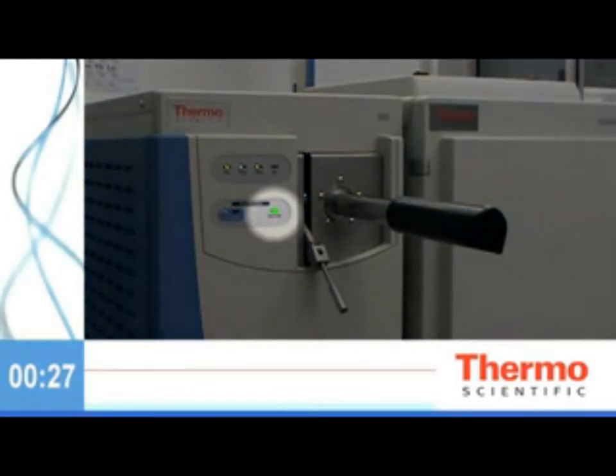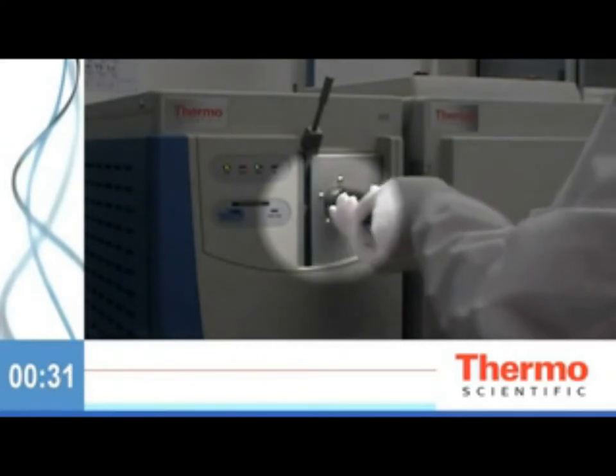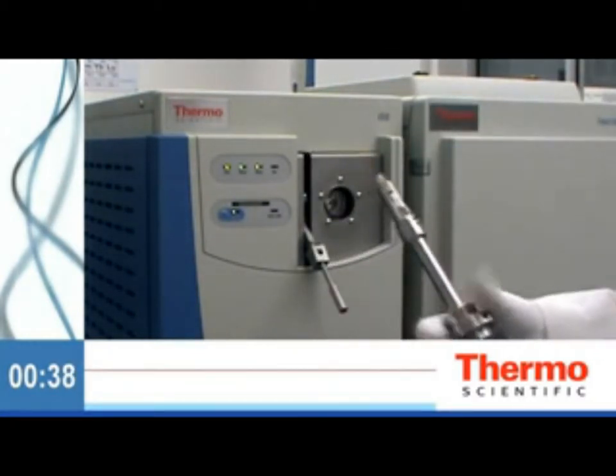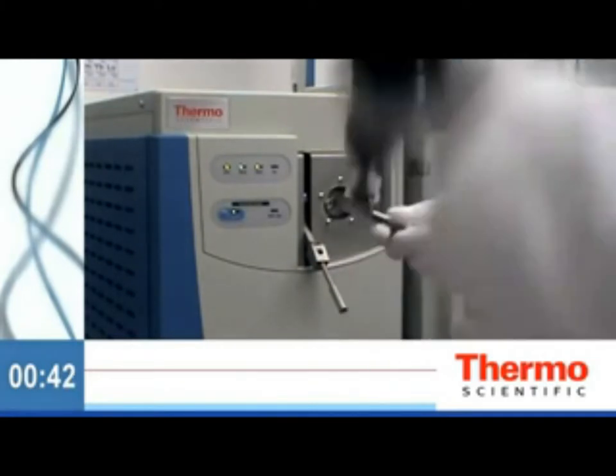When the ready-to-open light goes green, open the valve, insert the tool, connect to the ExtractaBrite cartridge, then retract it. You can't take the tool off while the valve is open. Close the valve and remove the tool.